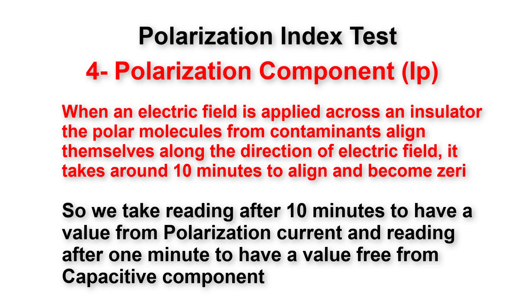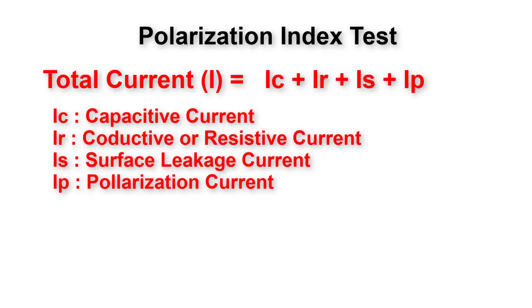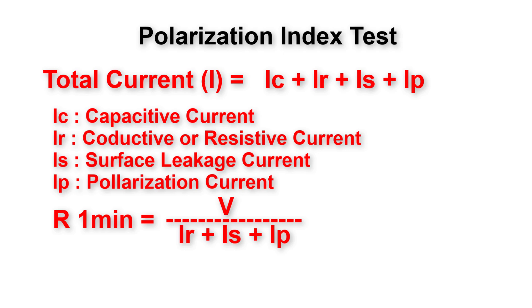We take the reading after one minute to have a value free from capacitive current. So the total current I equals: capacitive current Ic, plus resistive or conductive current Ir, plus surface leakage current Is, plus polarization current Ip. The megger reading at one minute is without capacitive current, so R(1 min) = V / (Ir + Is + Ip).